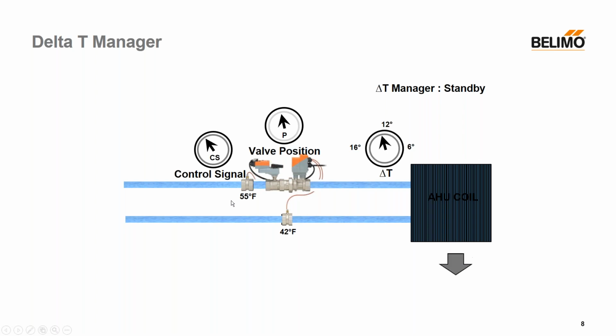I have a couple of dials above here. My first says CS, which is the control signal coming from the building automation system. The second one, right above my valve, is the valve position, or the P dial. And the last one, to the right by my coil, is my actual delta T. So we can see here, everything is at design or close to design. So our system is pretty happy. 42 comes in, 55 comes out on my water temp. I have a nice heat transfer happening.